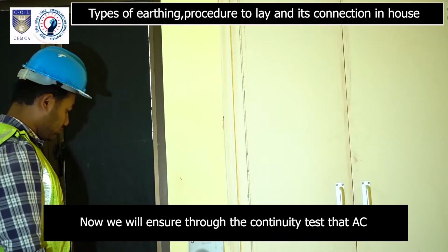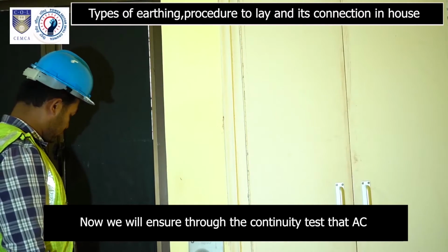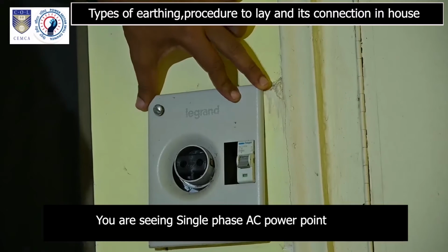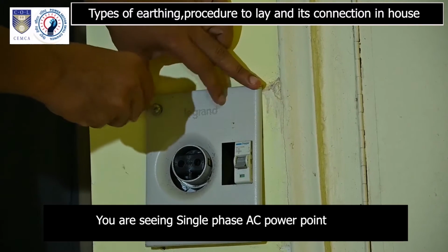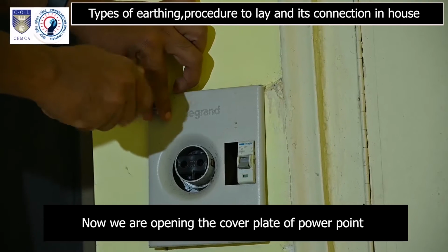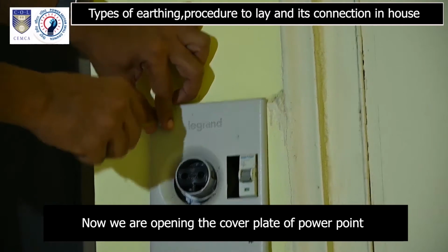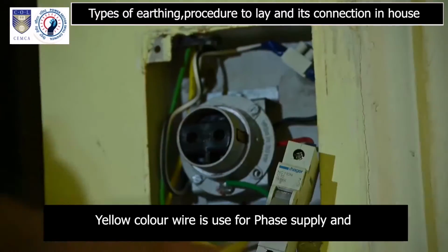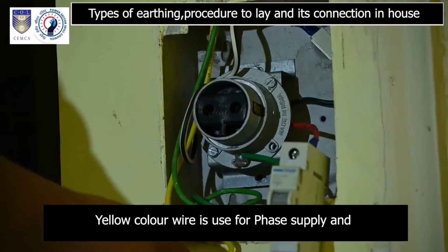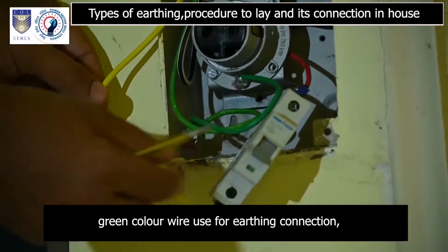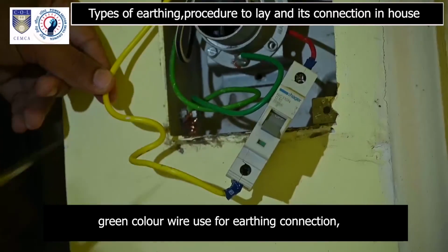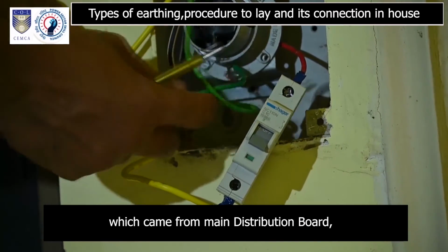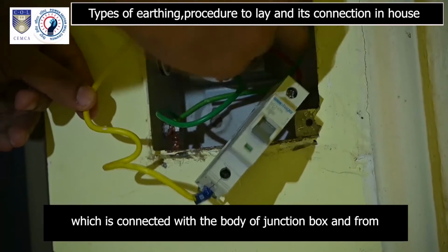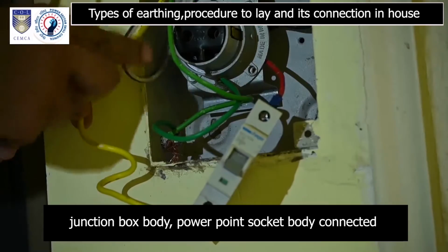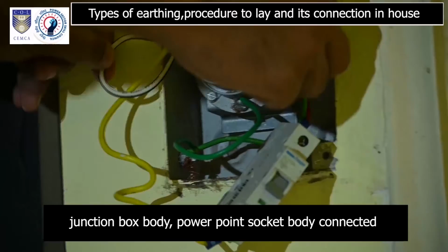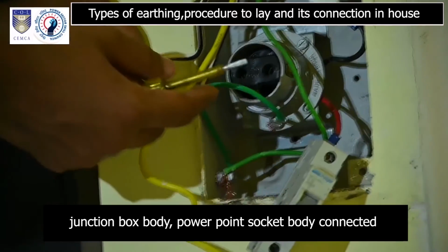Now we will ensure through the continuity test that the AC power point is properly connected to the earth wire. You are seeing a single phase AC power point. Now we are opening the cover plate of the power point. Yellow color wire is used for phase supply and green color wire is used for earthing connection, which came from the main distribution board and is connected with the body of the junction box, and from the junction box body, the power point socket body is connected with the earth wire.